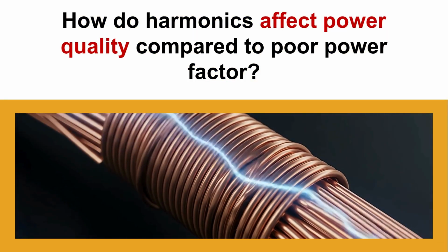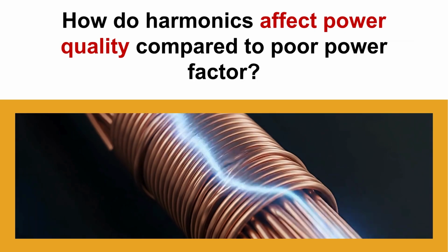A power factor, on the other hand, is a measure of how efficiently a site uses the power it draws from the grid. So a poor power factor typically indicates that the site is drawing a lot of reactive power from the grid compared to the amount of active power it draws. So they're two separate concepts, really. Harmonics do influence the power factor of a specific site. Like I explained before, harmonics is basically a power quality issue.